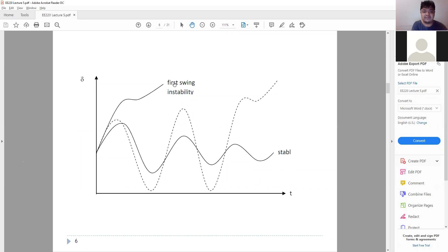Now we also have what we call voltage stability, which is the ability of a power system to maintain steady, acceptable voltages at all buses of the system after being subjected to a disturbance from a given initial operating condition. The sequence of events that causes voltage instability will lead to a blackout or abnormally low voltages in a significant part of the power system. That is what we call voltage collapse.